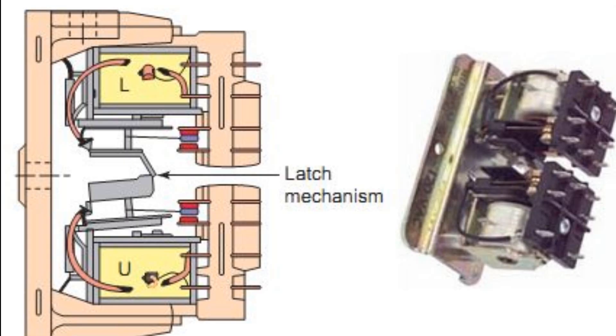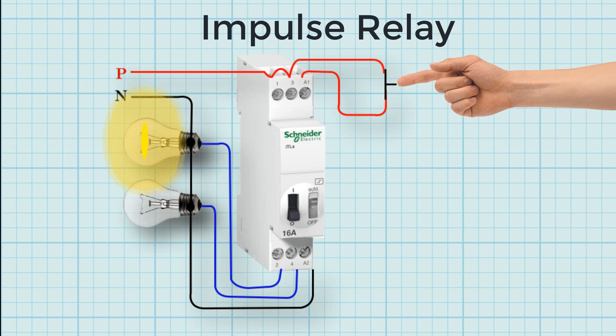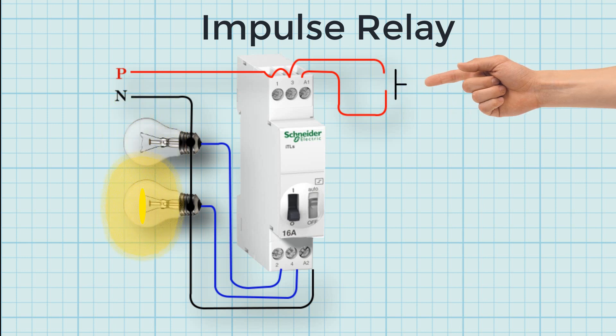That, upon application of power, determines which position the relay is in and energizes the opposite coil. This is a two-position electrically actuated switch that maintains either contact position independently, without any power being sent to the coil, other than a single pulse to change the position of contacts.